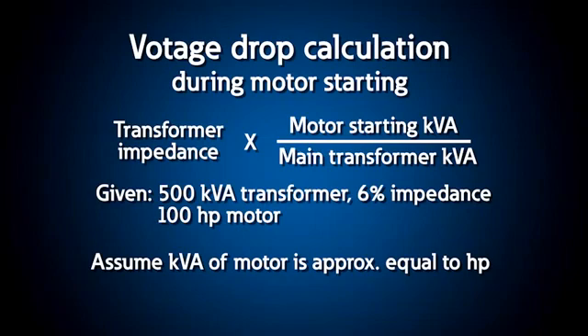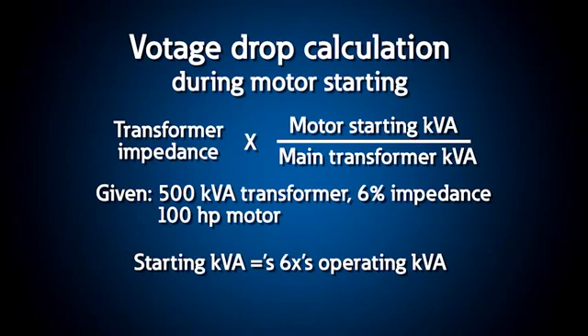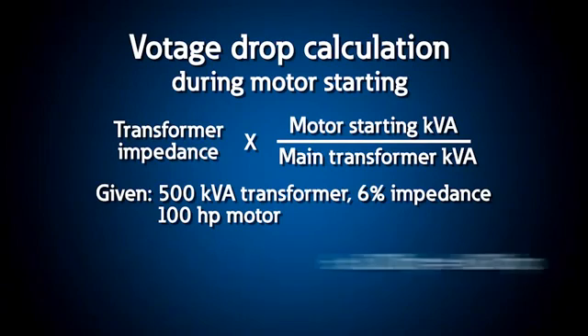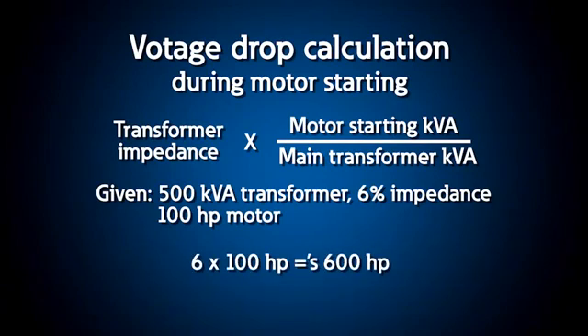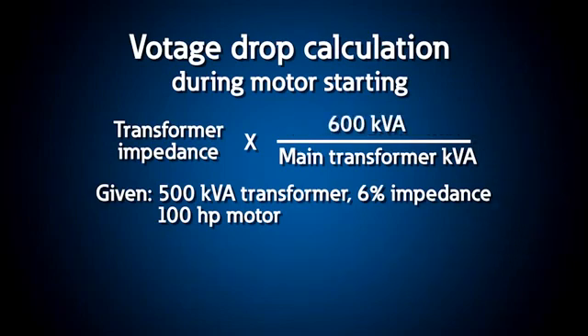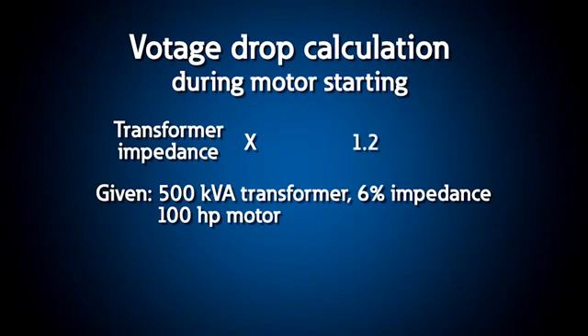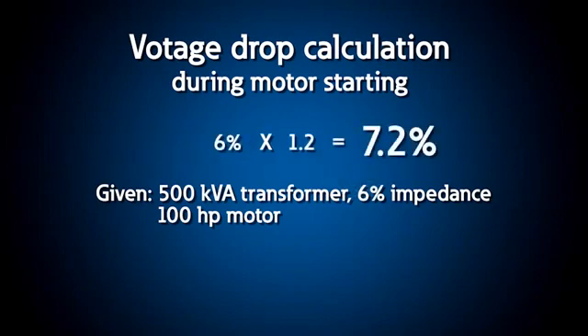Then, for a 100 horsepower motor, estimate the starting kVA at 6 times the operating kVA of 100, resulting in a starting kVA of 600. The ratio of motor starting kVA to transformer kVA is 1.2, so the voltage drop across the main transformer during starting will be 1.2 times the transformer impedance, or 7.2%.